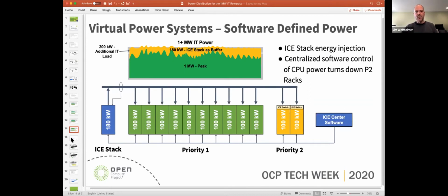And software here is consistently monitoring the state of charge and the state of health on the energy storage systems, the load on the electrical systems and the individual racks, and it's comparing all that against the electrical system capacity to make changes to the policies that decide where power is routed. So the software monitoring and the control paired with those hardware devices creates the ability to dynamically or programmatically control the systems to pull the typically unusable capacity for other racks.